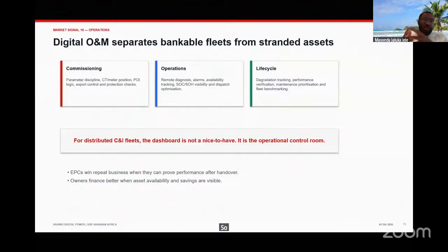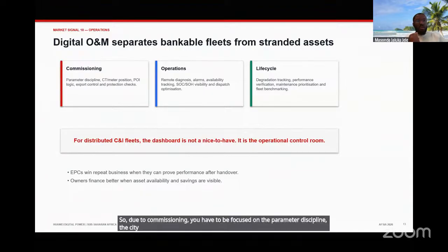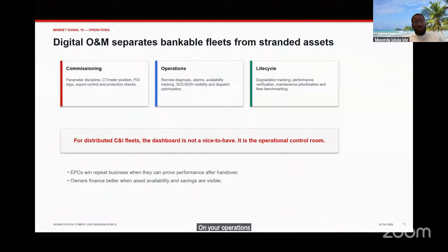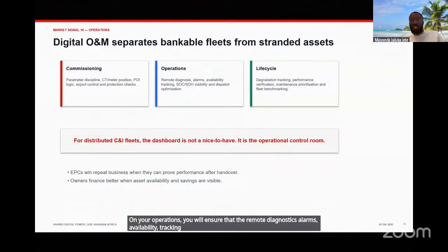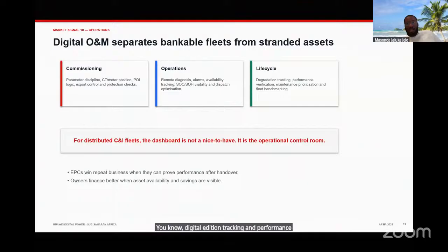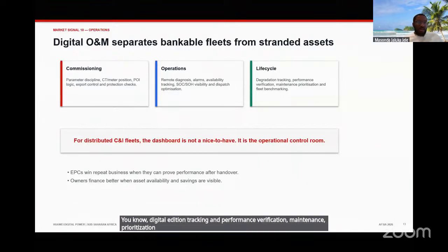For commissioning, you have to focus on parameter discipline, the CT meter positioning, your POI logic, your export controls, and protection checks. On your operations, you ensure that remote diagnostics, alarms, availability tracking, SOC and SOH visibility, and dispatch optimization are done. From a lifecycle perspective, you have degradation tracking, performance verification, maintenance prioritization, and fleet benchmarking. For distributed C&I fleets, the dashboard is not a nice-to-have. It is the operational control. This is on your O&M side.